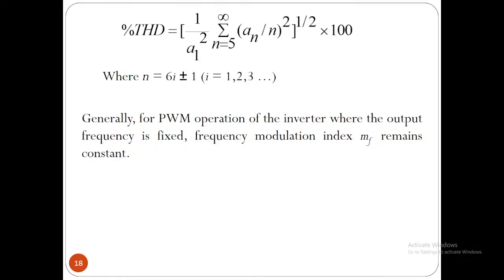Why do we consider from n equal to 5? While computing the percentage THD—say up to the 30th or 25th harmonic—we start from the 5th, not the 3rd. The reason is that the 3rd, 9th, and other triplen harmonics are automatically eliminated in a balanced three-phase system, which is what we're dealing with. Even harmonics are also absent due to symmetry, so only odd, non-triplen harmonics remain. That's why we consider the 5th, then 7th, skip the 9th, then 11th, and so on—chosen as n equal to 6i plus or minus 1.